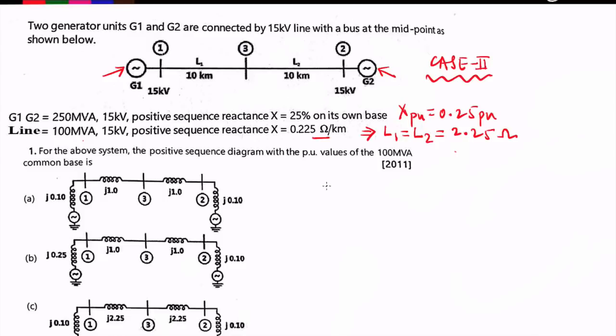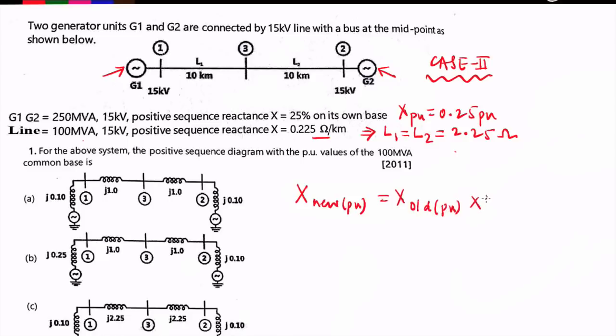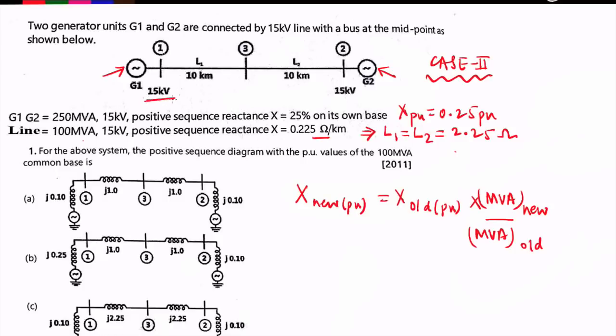By taking 100 MVA as the new base, we need to find the new reactance of both generators. Their reactance is given as 0.25 pu at 250 MVA base. The formula is: X_new (pu) = X_old (pu) × (V_base_old / V_base_new)² × (MVA_new / MVA_old). Since the new and old base voltages are both 15 kV, the voltage ratio squared equals 1, so it cancels out.